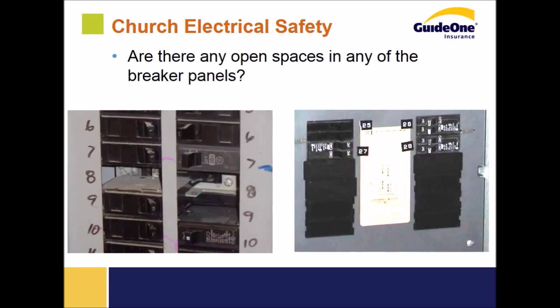In the image on the left, we've got some missing blanks, some open spaces, and there's a serious electrocution hazard here. You're intended to switch these breakers on and off, so your hands are dangerously close to live current, and it's also possible for dust, debris, and rodents to get in and cause issues. So there needs to be blanks installed if you see this type of thing, and the picture on the right shows the actual blanks installed to prevent access and prevent dust and debris from getting into the panel.